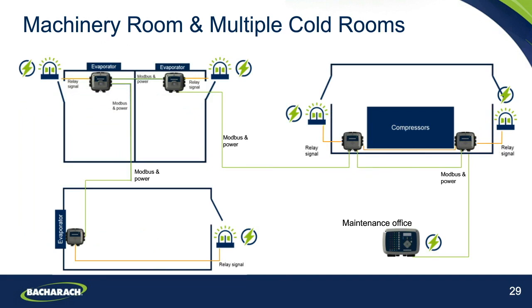We get into an even more complex system here, and we can look at a large machinery room with two entrances into there. And again, with that kind of space, we probably look at two detectors being needed there for best practice. But the most important thing in terms of code compliance, of course, is ensuring that we have the audible and visual alarms with the horn strobes outside of each of those entrances. The same is then seen in the cold rooms, running off the centralized refrigerating system. And as you can see, we have the gas detection in each of those. We have the horn strobes outside of them.